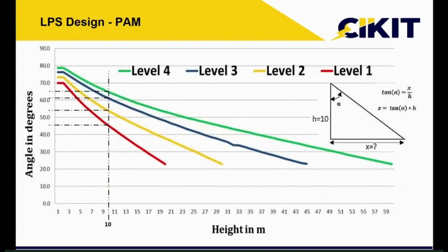So this is the graph provided by the standard for obtaining this angle for different heights. For example, if I take 10 meters of height, then I have to extend a line from 10 meters, and if I'm going for level 1 protection, I have to take this angle, that is the point where it is intersecting this level 1. If I'm going for level 4, I have to take the angle, that is the 10-meter line intersecting the level 4. So from this, we have to obtain the angle. Then by using this tan theta formula, we have to calculate the radius of protection.